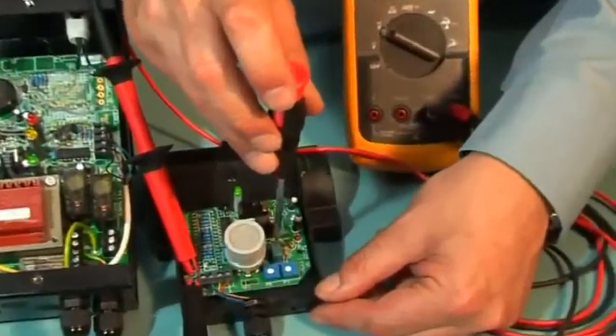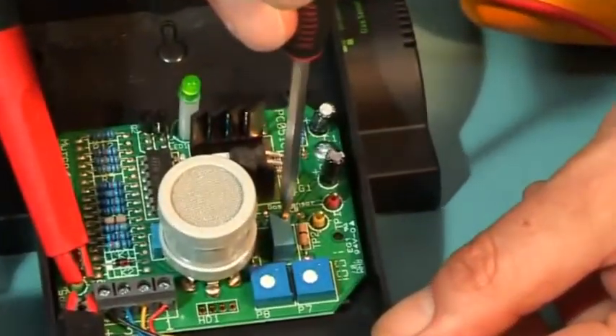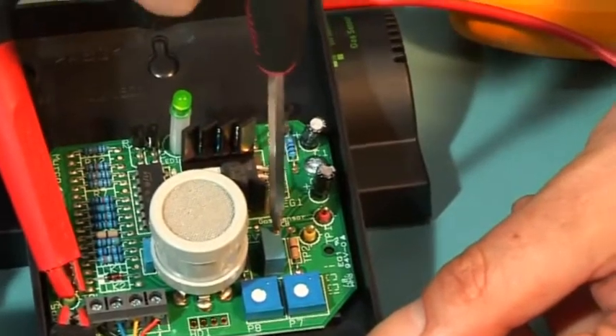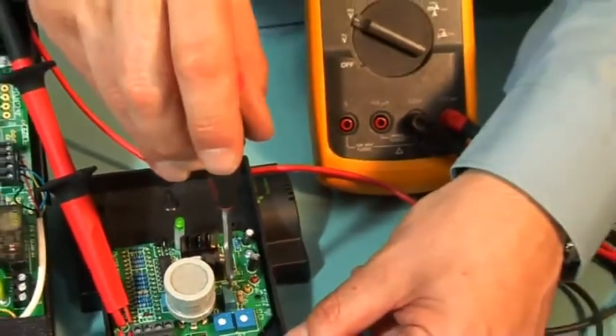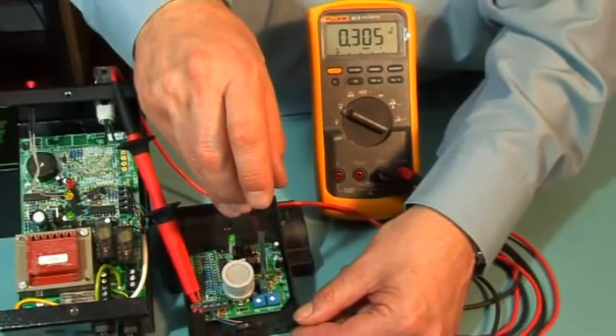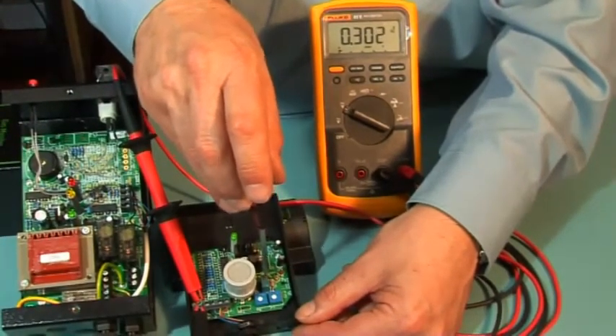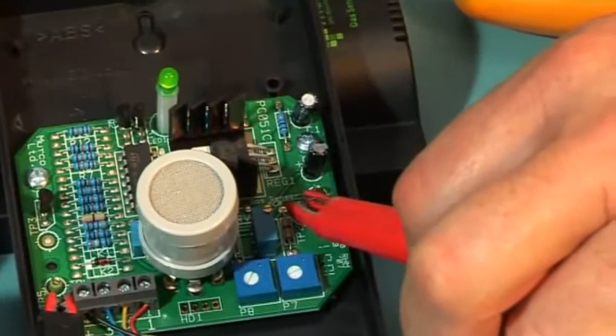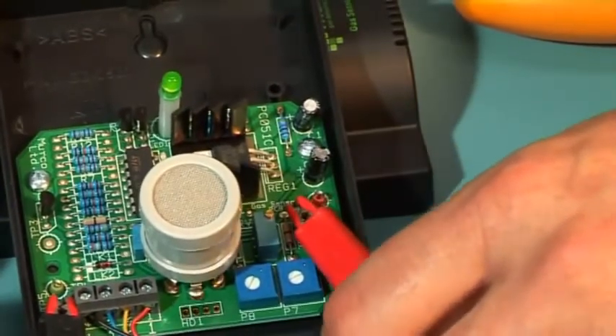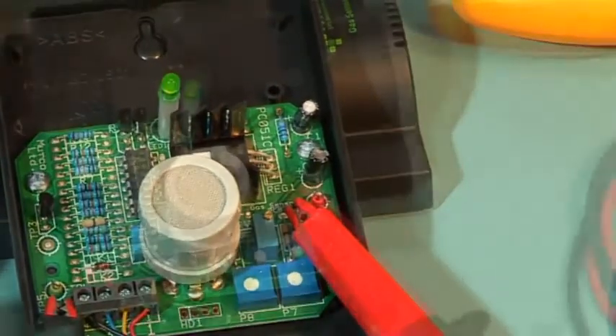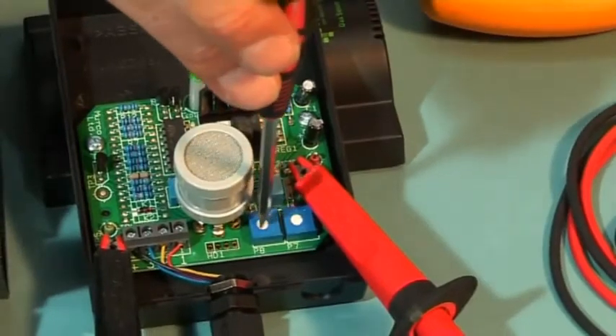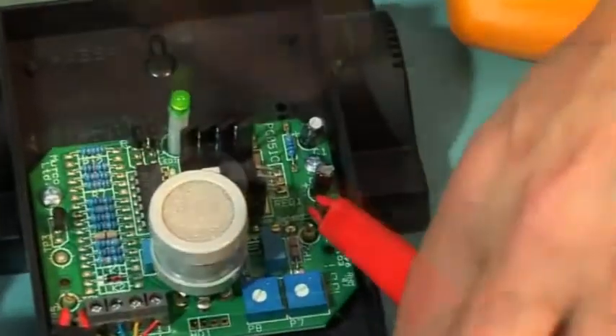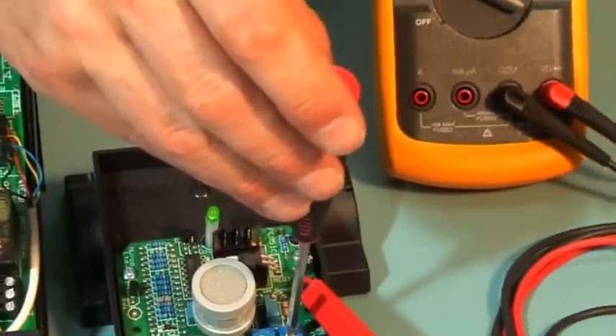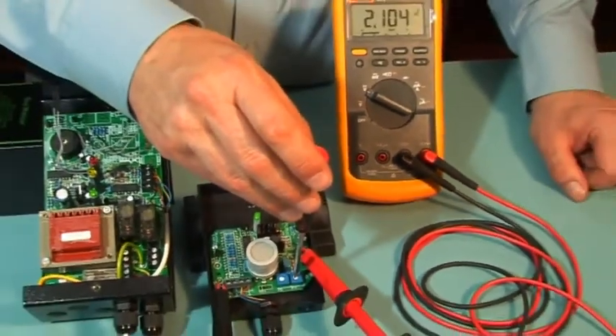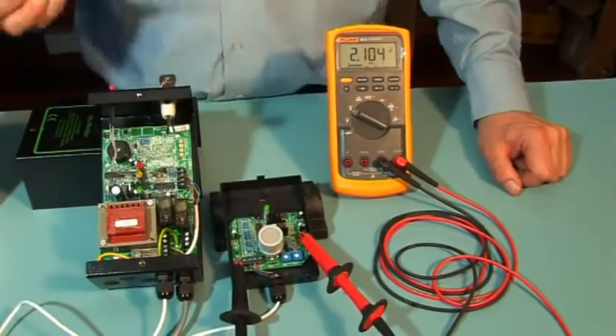If different to the label factory voltage, then adjust RV1 to the standby voltage, normally 0.3 volts, or as on the rating label. Move the positive lead from TP5 to TP2 and adjust P8 for the low level as shown on the rating label. Then move the positive lead from TP2 to TP1 and adjust P7 for the high level as shown on the rating label.